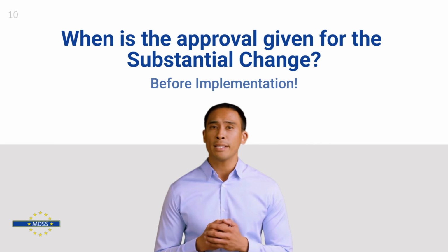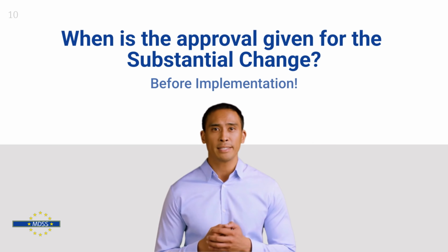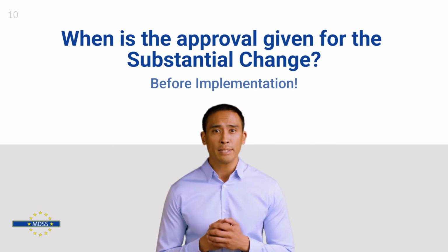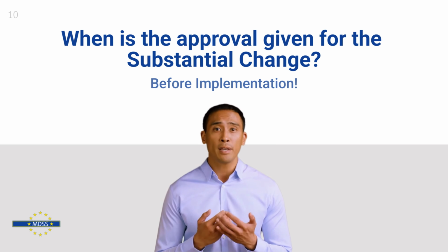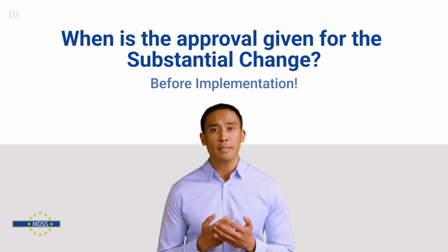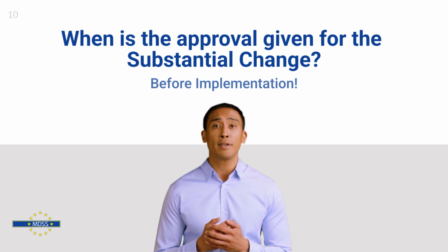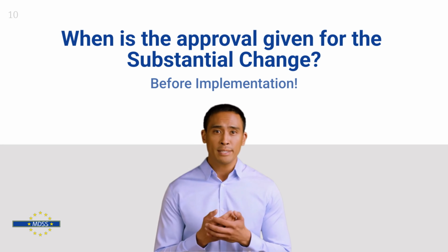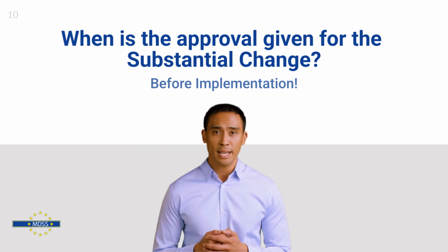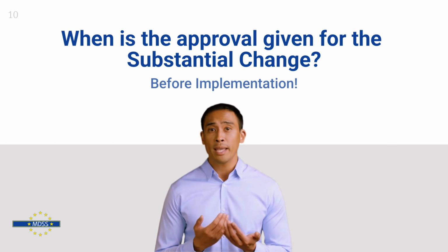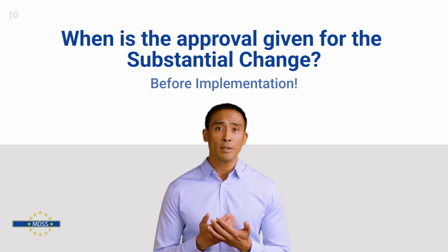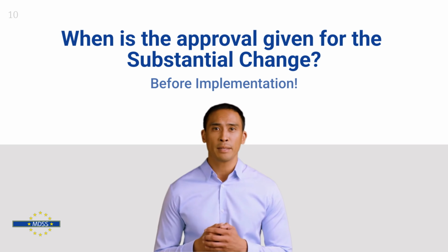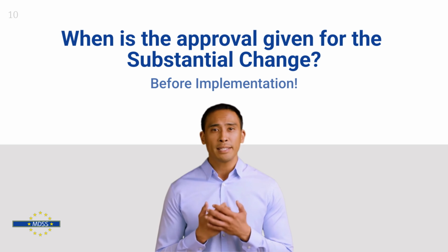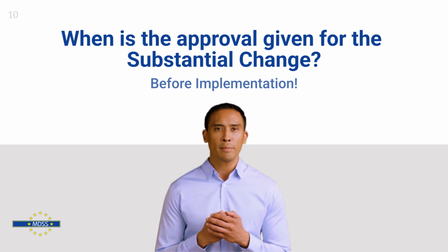The debate may be, when is the approval given with the supplement certificate? The process clearly outlines that the supplement to the certificate must be given before the changes are implemented. This is substantiated with the following. The manufacturer must inform the notified body of any plan for substantial changes to the quality management system. The use of the term plan is key here. It implies that notification and assessment are required before the change is implemented.